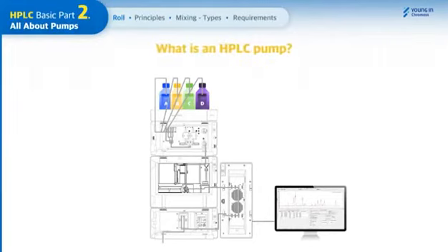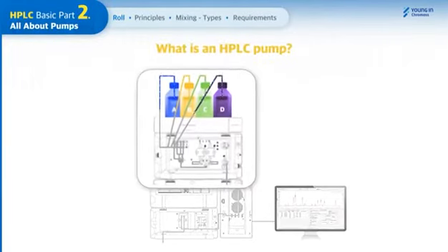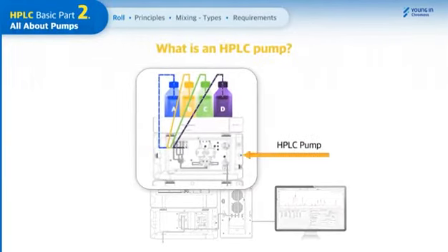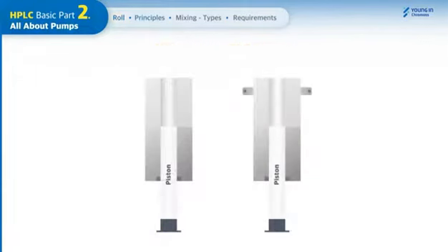HPLC pumps. Let's start with what an HPLC pump is. An HPLC pump is a solvent delivery module that draws the mobile phase from solvent bottles at the specified flow rate with composition to deliver the sample to the column. Modern pumps are configured with at least one pair of pump heads, including reciprocating pistons, and there are check valves on the pump head which allow the mobile phase to flow in one direction, not in a reverse way.